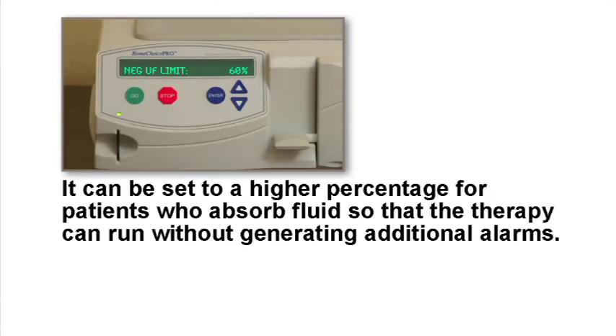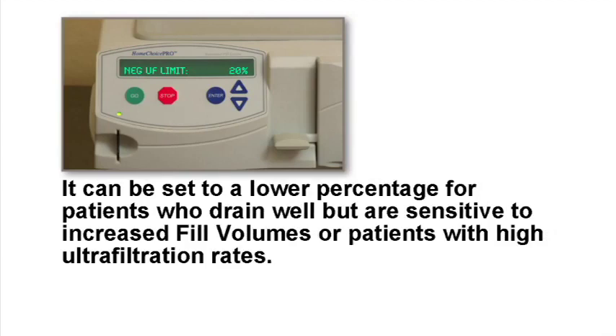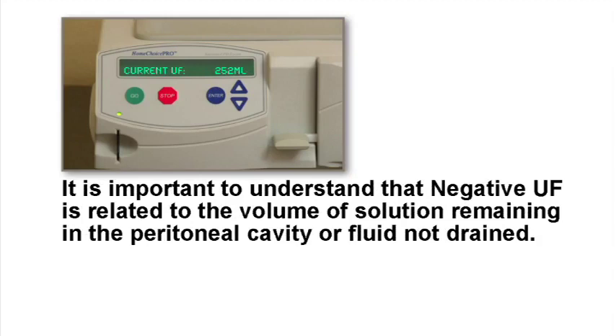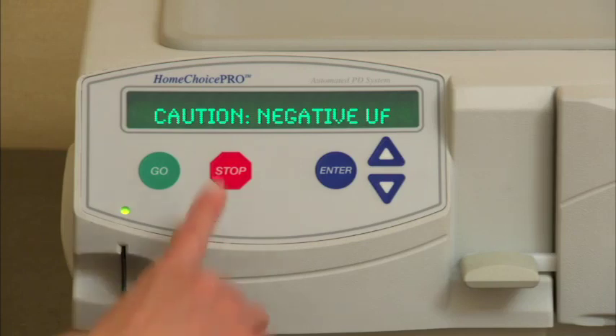It can be set to a higher percentage for patients who absorb fluid so that the therapy can run without generating additional alarms. It can be set to a lower percentage for patients who drain well but are sensitive to increased fill volumes or patients with high ultrafiltration rates. Negative UF is related to the volume of solution remaining in the peritoneal cavity, or fluid not drained from the fill volume. This is a manual restart alarm, which means you must manually stop the alarm and correct the situation.